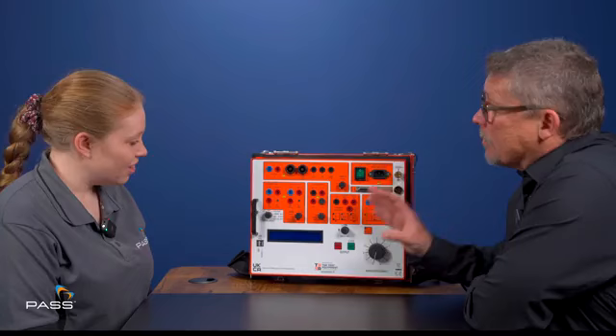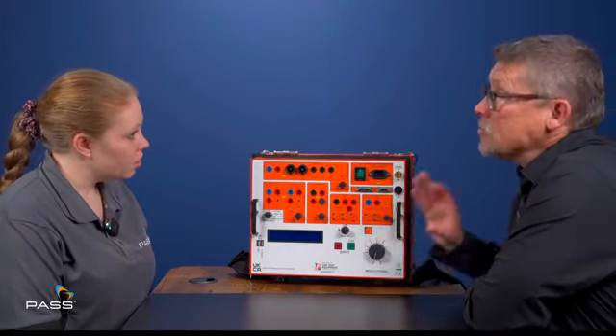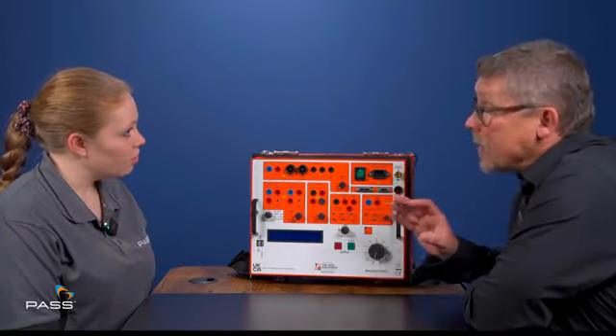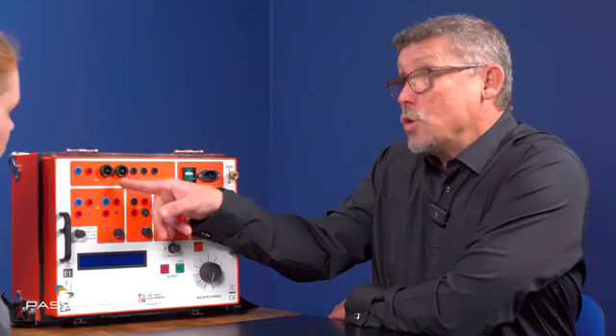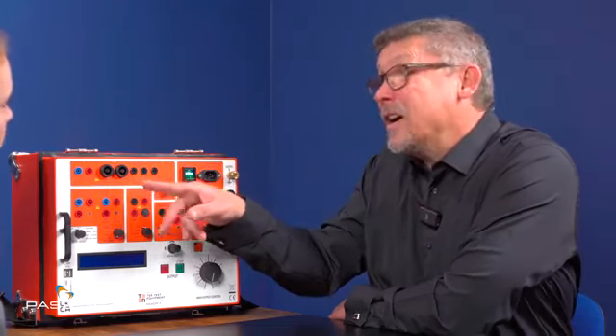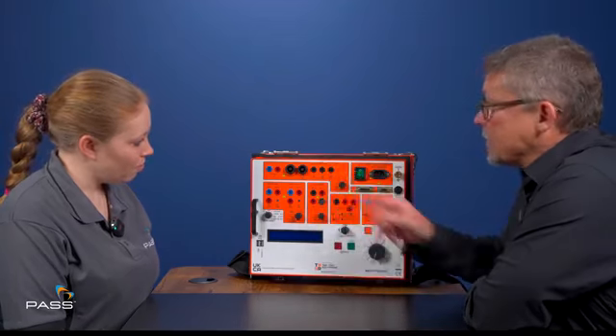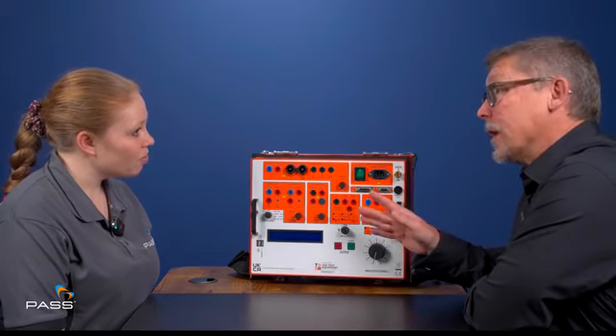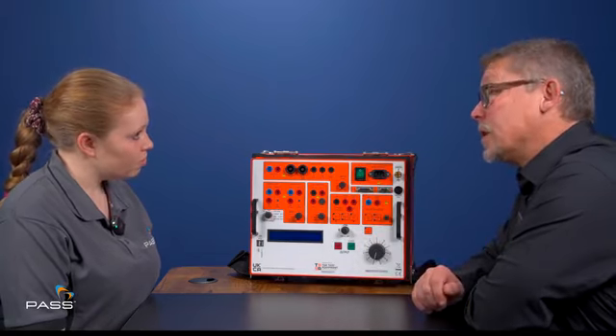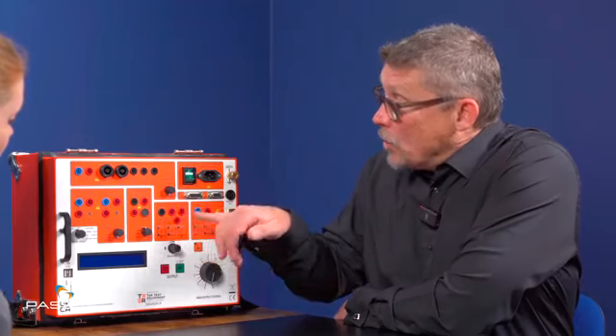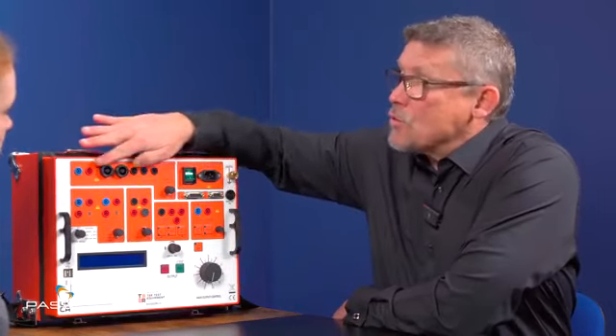The next thing that we've got on here, because as I said, secondary current injection test sets are designed for the older electrical mechanical relays. They're big, they're clunky. You know, your 200 amps at 10 volts, that's a lot. That's 2000 VA. If you're looking at a digital relay test set, you look at 30 VA per channel. The secondary channel with this gives us the ability to also test digital relays, which is unusual in a secondary injection test set.